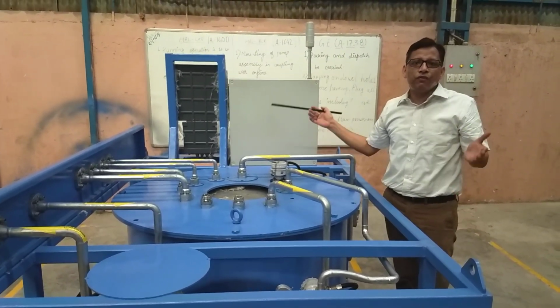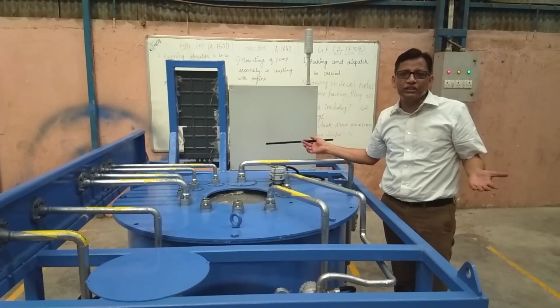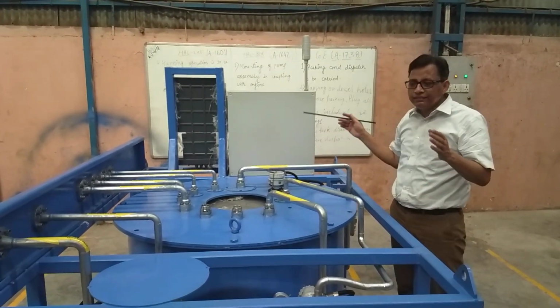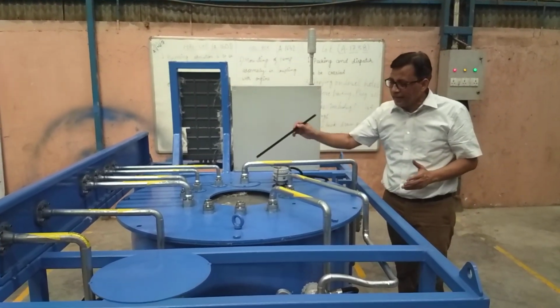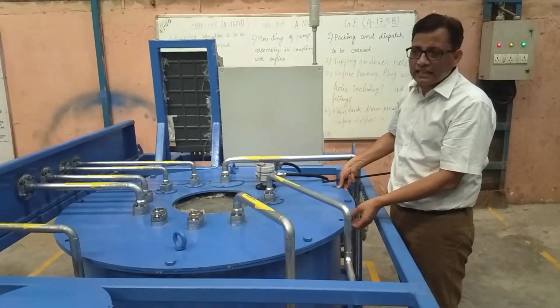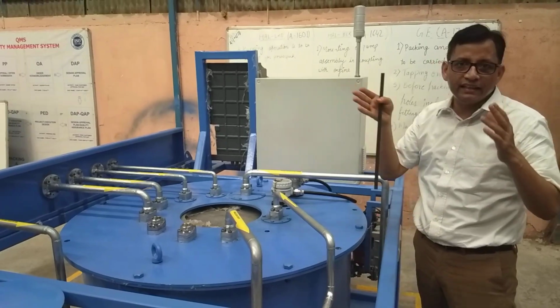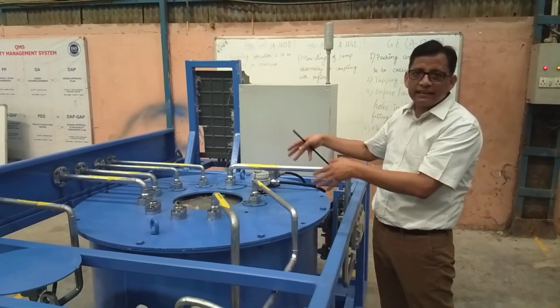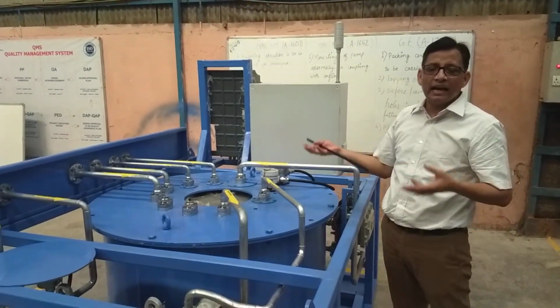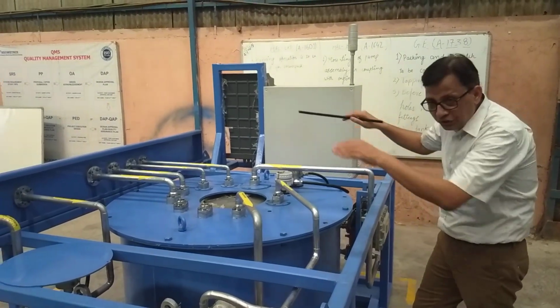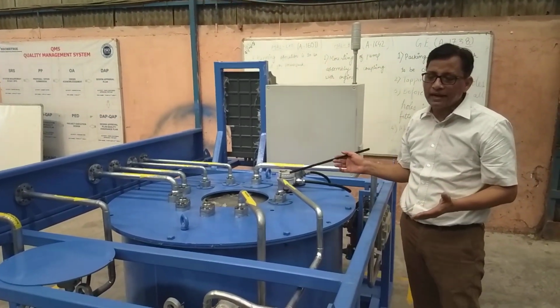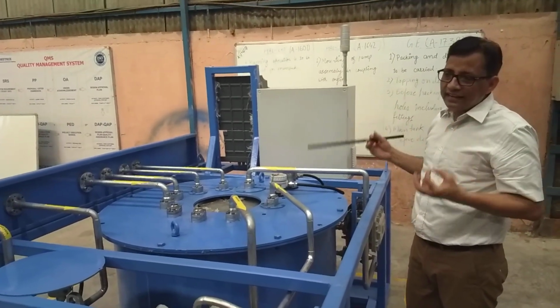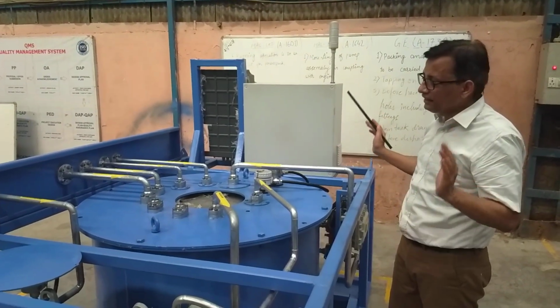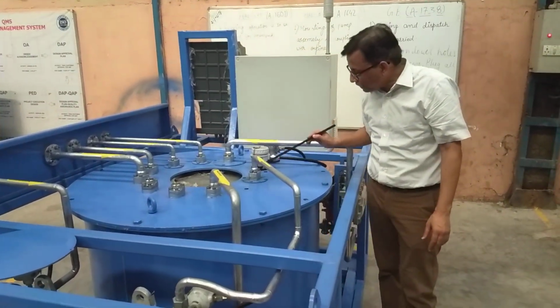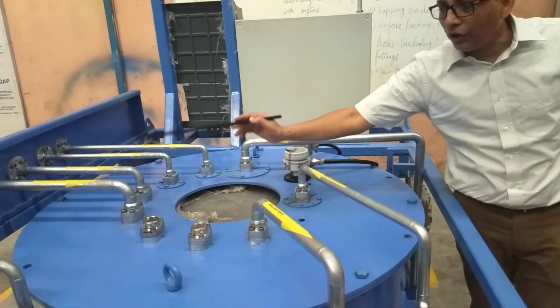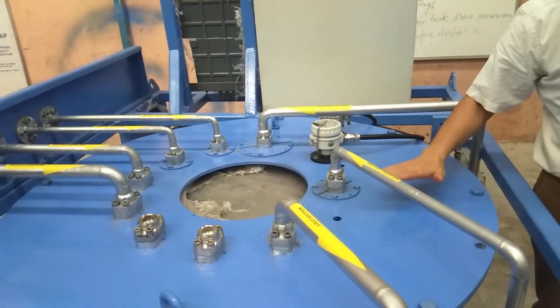So this fuel traction specific fuel consumption measurement system that you see is for the loco engines, for 6000 HP loco engines, for 5000 HP loco engines. This system is used, and as I explained, the tank is kept inside this heavy metallic cover so that it is isolated from wind outside or from the vibrations outside. The tank is kept on the 4 load cells, which in turn are kept on anti-vibration pads, and that tank is put on a foundation which again is sitting on anti-vibration pads. So the tank weight weighing system is always measuring only the weight and nothing is influencing it. All these pipelines which are going inside are not touching the tank body in any manner. These are hanging from this tank top cover.